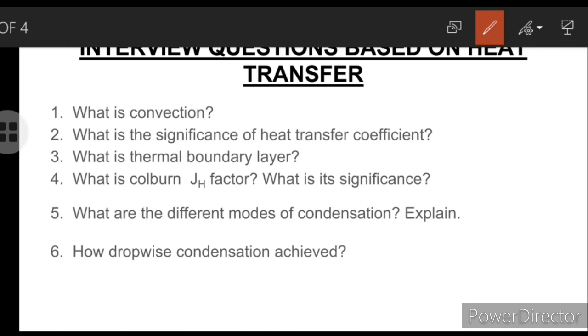In film condensation, the initially formed drops quickly coalesce and spread as a film on the solid surface. The film acts as a barrier for heat transfer to condense more liquid, thus offering more resistance to heat transfer than dropwise condensation. Consequently, heat transfer coefficients are far less for film condensation than for dropwise condensation. Film condensation is the normal mode in practice and is therefore assumed in heat transfer estimates for design purposes.